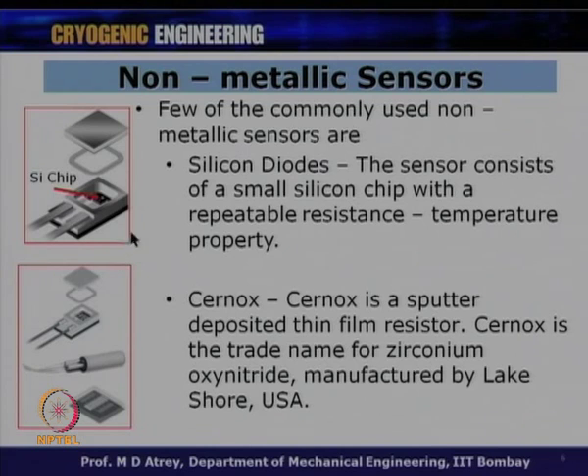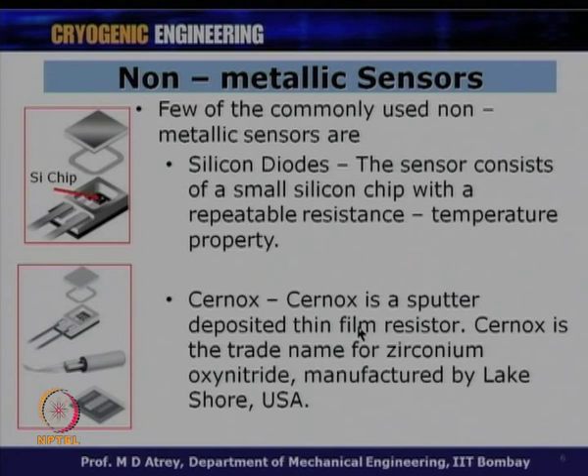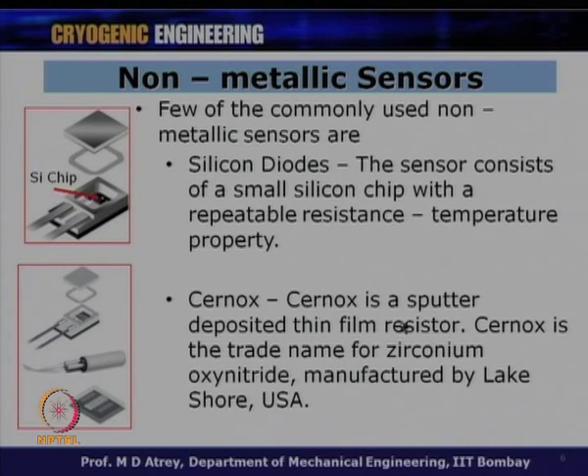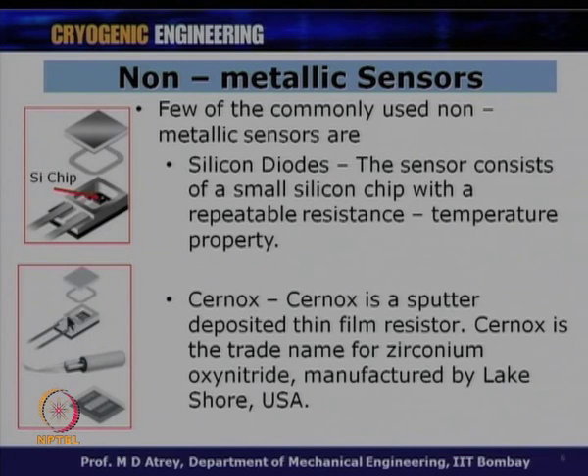Next is Cernox, which has a similar appearance to a silicon diode. Cernox is a sputter-deposited thin film resistor. Cernox is actually a trade name for zirconium oxynitride manufactured by Lakeshore, USA. The sensor is housed in a small casing. A third category is ruthenium oxide — a thick film resistor widely used in magnetic field applications, working on the same principle of resistance changing with temperature.